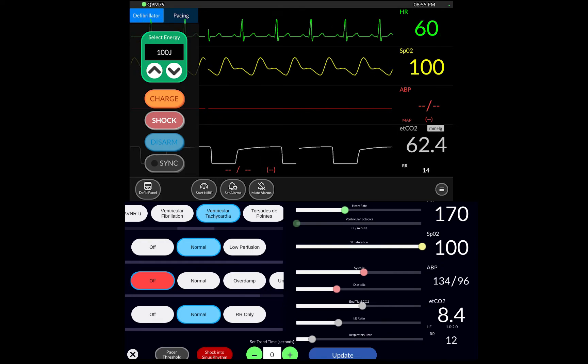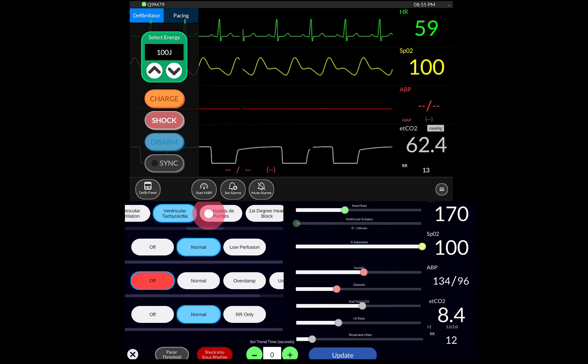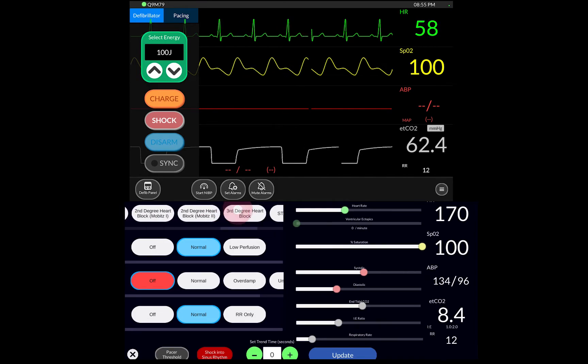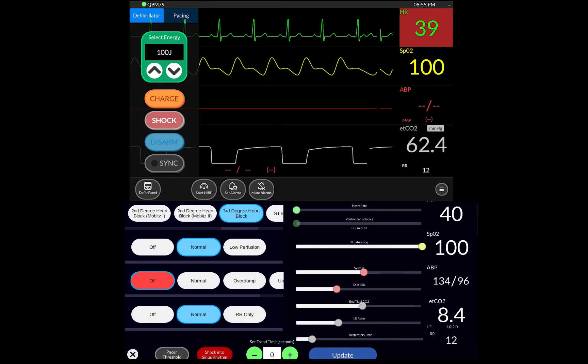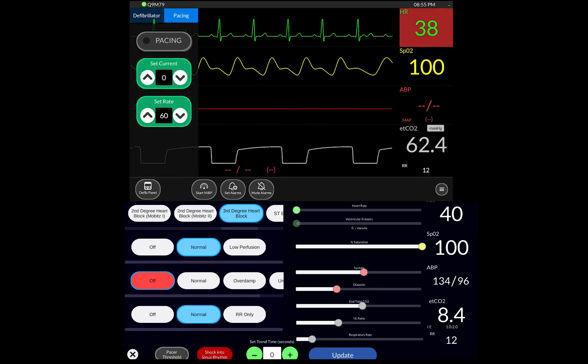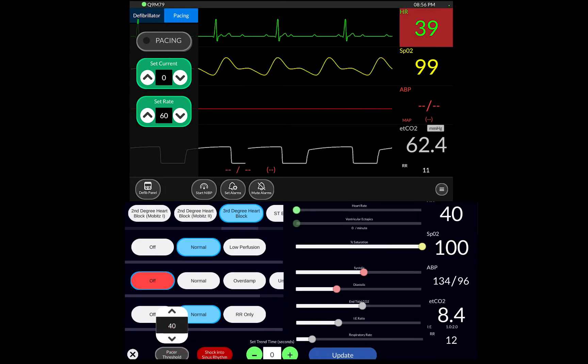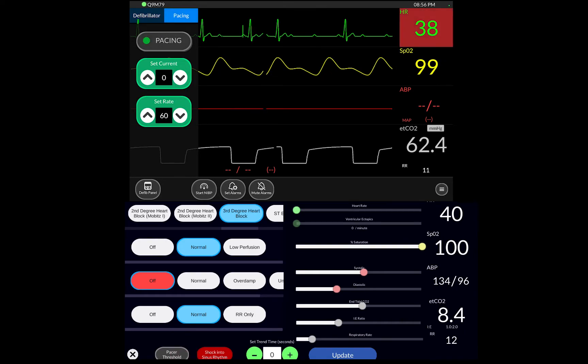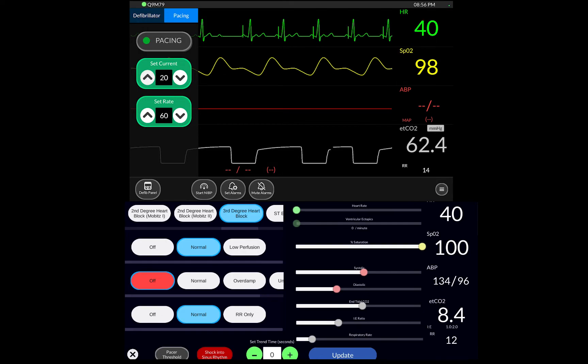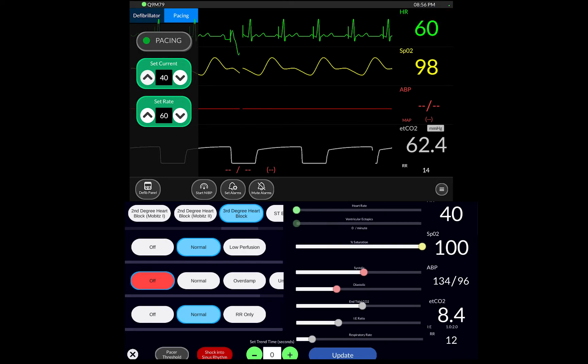Then if you want to pace, there's all of your heart blocks here. So there we go. If we want to pace, just go to pacer on the monitor. We hit pacer. Before that, we can also change our pacing threshold. So I can set my pacing threshold to 40. If I start the pacer I can go up by 10. We all know how this works. And we go over there. And there we go.